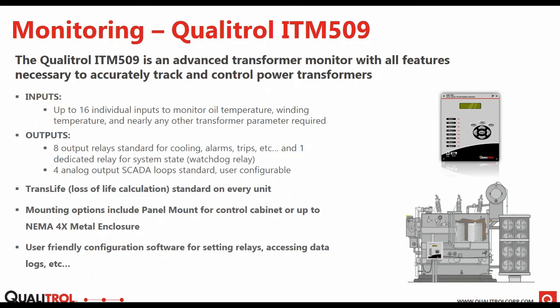It has a built-in loss of life calculation, which is standard on every unit. We can do it in a panel mount or a control cabinet, or a standalone enclosure, which is really good for retrofits. It's fully configurable, and it has a configuration software for setting relays, accessing data logs, and things like that.